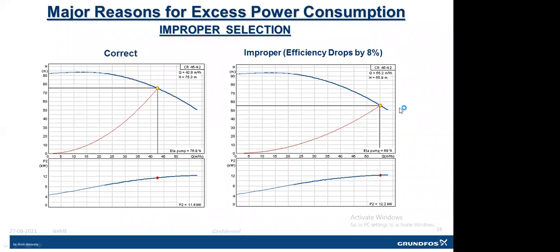So while designing the pump, first we need to finalize the flow and head. First establish the flow, how much flow is required, then calculate the head by calculating static head and dynamic head. The static head will anyway be constant, but for calculating the dynamic head, first finalize the flow, and for that flow calculate the dynamic head. Once we establish flow and head, select the pump at the best efficiency point, so we can avoid the energy losses in our system.